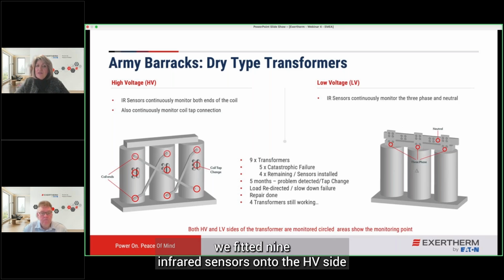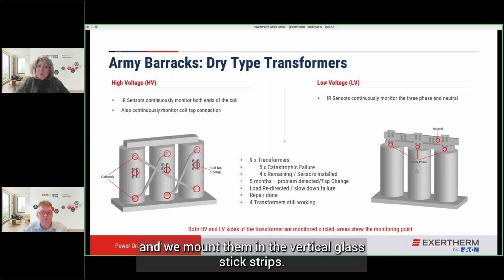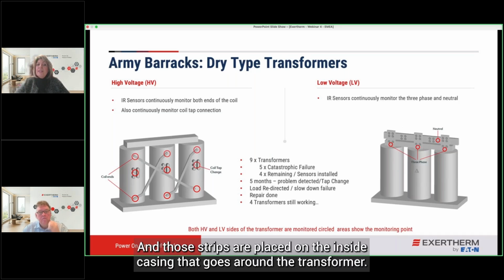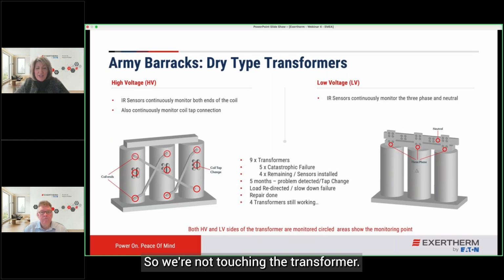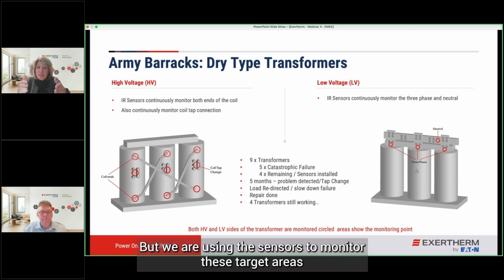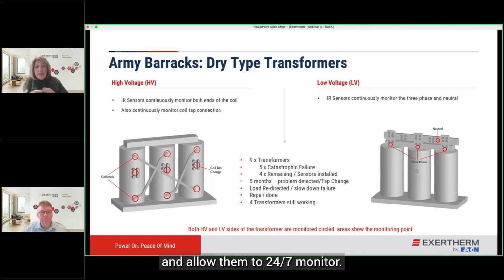As per what I just said, we fitted 9 infrared sensors onto the HV side, and we mount them in the vertical plastic strips, and those strips are placed on the inside casing that goes around the transformer. So we're not touching the transformer, we're not impacting on any type test, we're not touching it in any way, but we are using the sensors to monitor these target areas 24/7.